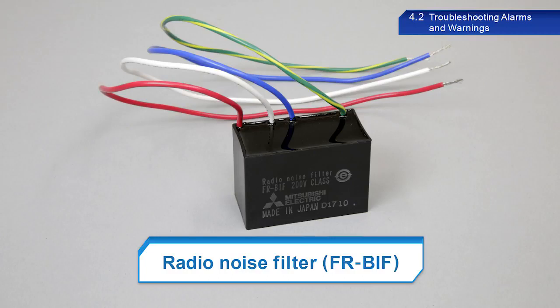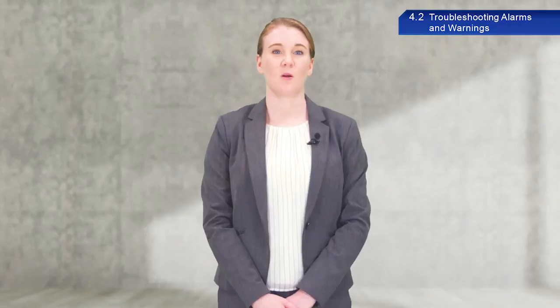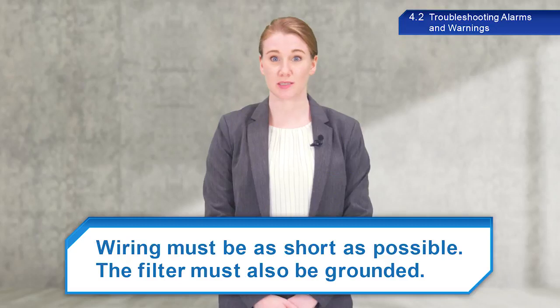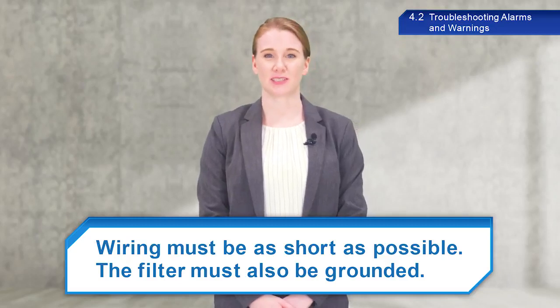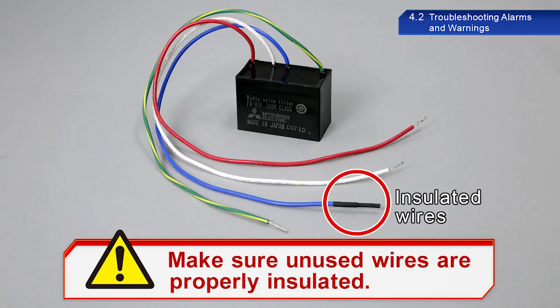The FR-BIF radio noise filter reduces noise generated by the servo amplifier power supply. Wiring must be as short as possible. The filter must also be grounded. When using the FR-BIF with a single-phase power supply, make sure unused wires are properly insulated.